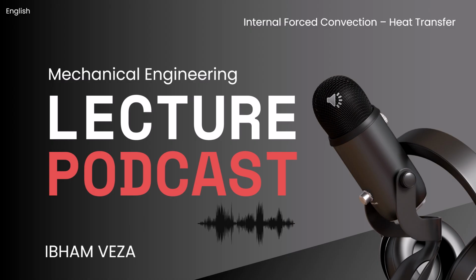Fourth power. Seriously, what does that mean practically? It means if you double the pipe diameter, keeping everything else the same, you can get the same flow rate with only 1/16 the pressure drop. Or, for the same pressure drop, you get 16 times the flow. 1/16 the pumping power. That's incredible leverage. It's huge. A massive consideration in design.